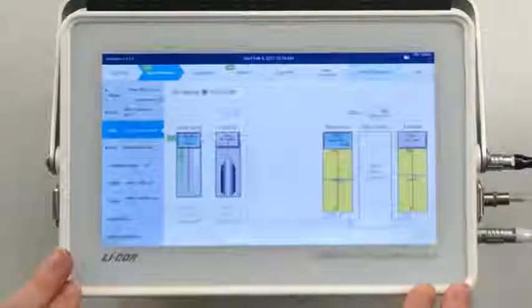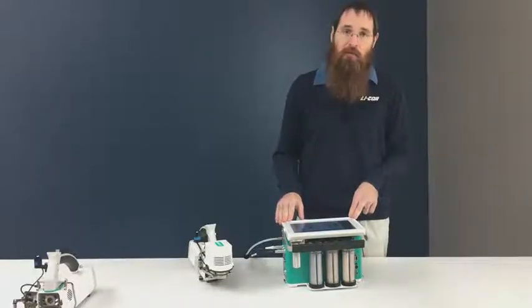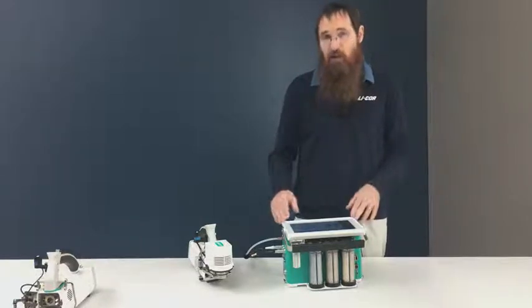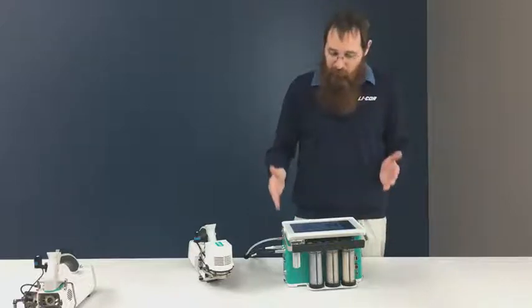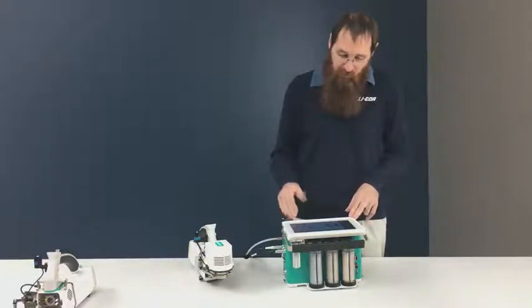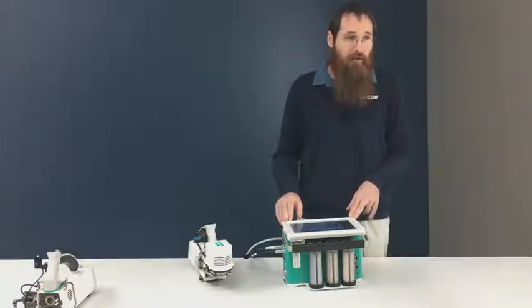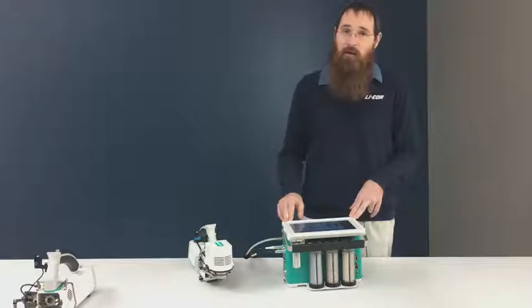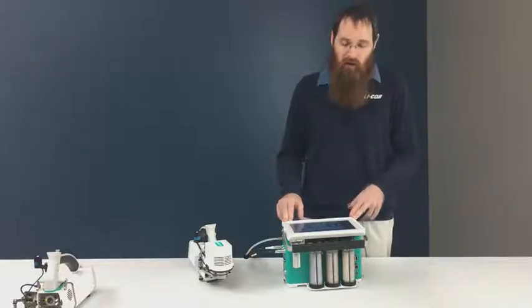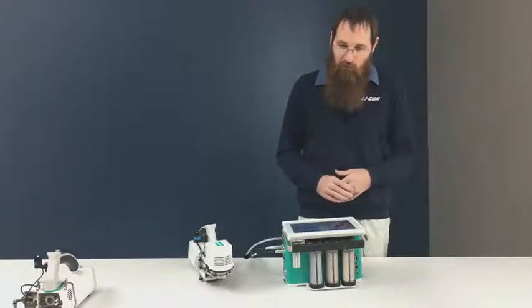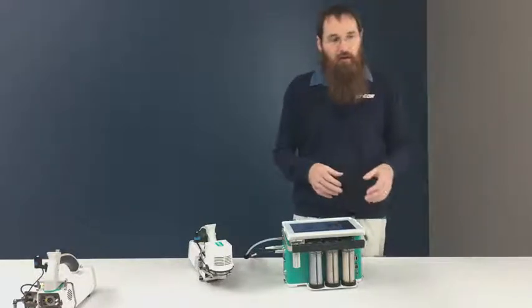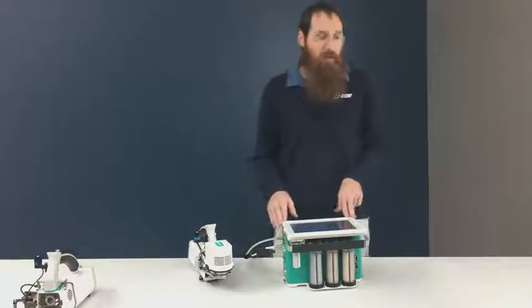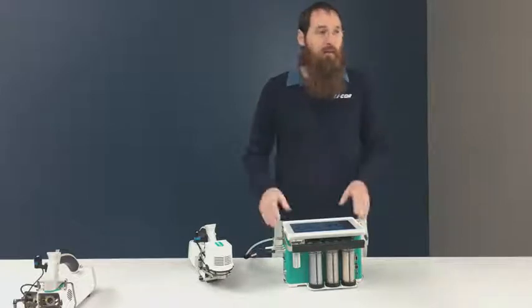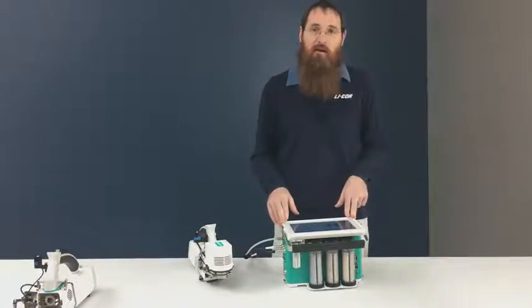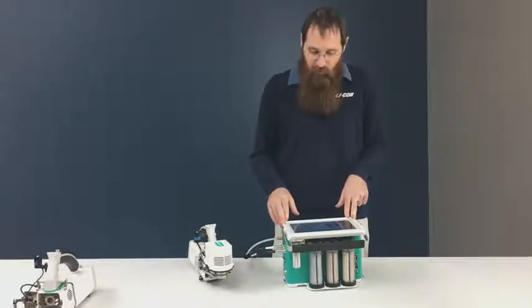And I did this deliberately because this is one of the really cool features of the 6800, right? I have full control of CO2 from essentially 0 ppm to 2000 ppm. And I can control at pretty much any concentration I want in between there. So if I want to control at 10 ppm, I can control at 10 ppm. If you were a 6400 user and you wanted to control at 10 ppm, well, you'd be pretty much out of luck, right? Because the way the injector was configured in the 6400, you got control at 0, and then you got control at something in the 30, 40, maybe 50 ppm range, depending on your instrument, and you couldn't do anything in between without heavy user modification to the console, and there were trade-offs for that modification.